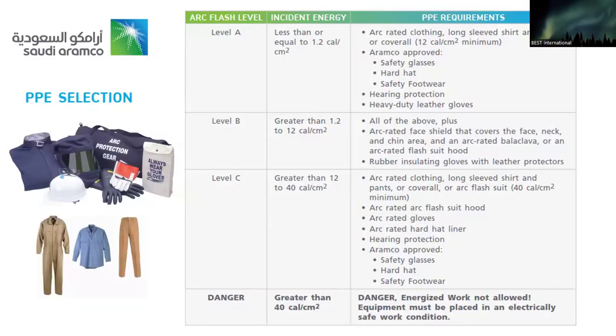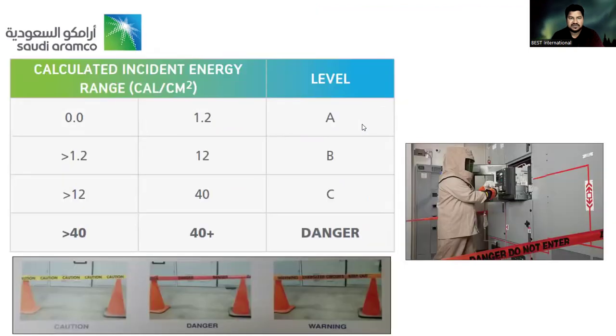Okay, guys. So the PPE selection is critically important as per the levels. We discussed in the previous slide, there are levels calculated based on the calories per square centimeter: caution, danger, or warning. All we need to decide is according to the calculated incident energy range.